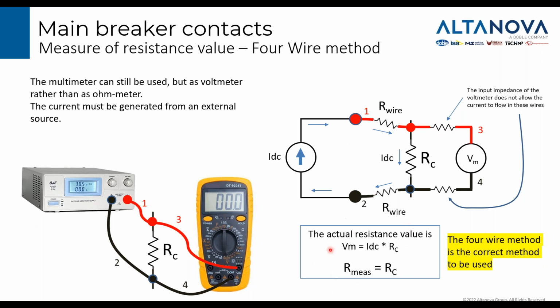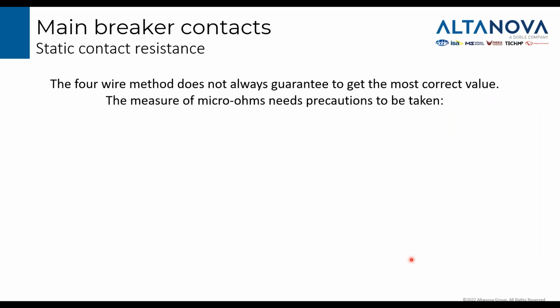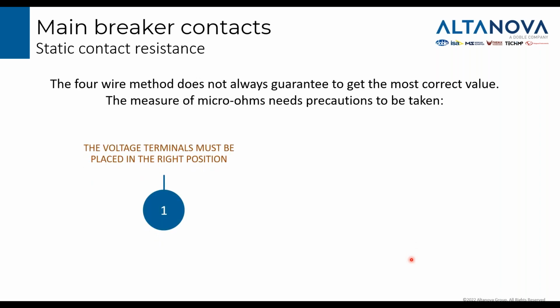Again, you measure the resistance by measuring the current and the voltage, and then you apply Ohm's law and you get the value that you're looking for. The four-wire method is mandatory, but is not enough to guarantee the most correct value. Some precautions must be taken. First, you have to pay attention to where you place the clamps, the terminals for the voltage measurement. If you make a mistake, then you get wrong values.